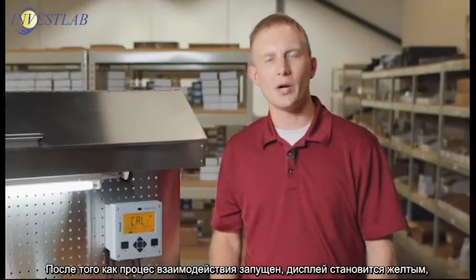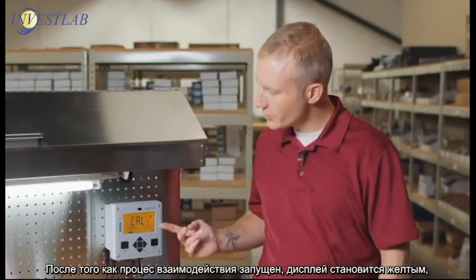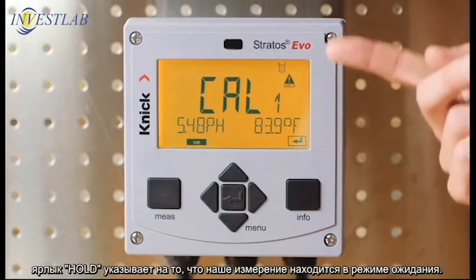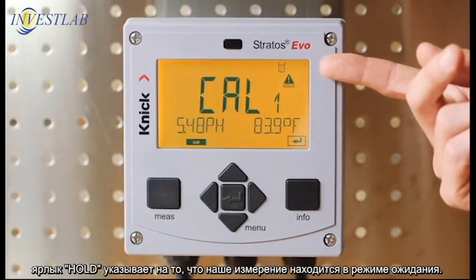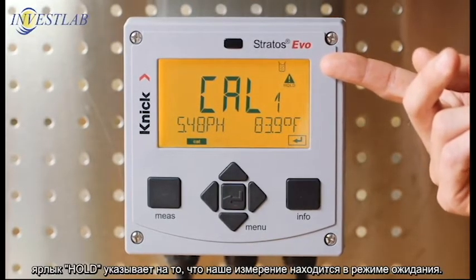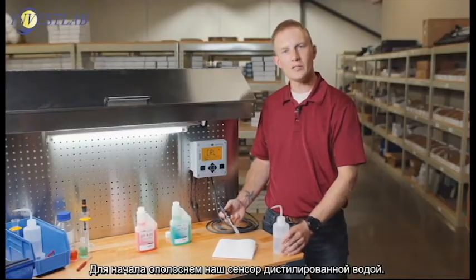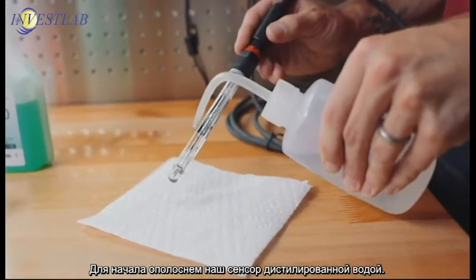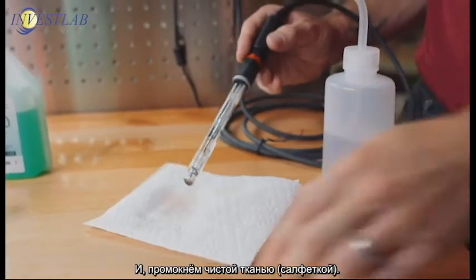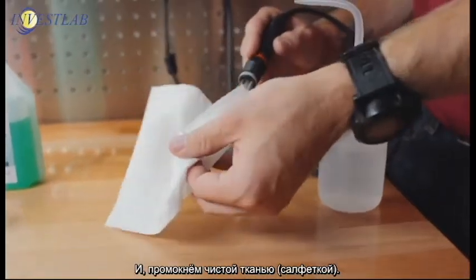Once the calibration process begins, you can see that our transmitter screen is turned yellow and the hold icon is displayed, indicating that our output to our control room is being held. First, we'll rinse our sensor with distilled water and dab dry with a clean cloth.